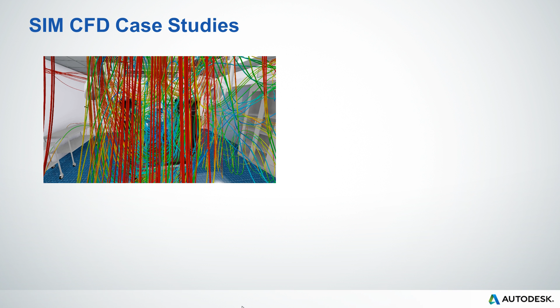The design of several configurations allows comparison of airflow patterns and provides an understanding of the sensitivity to various inputs and conditions. In this case, 8 different types of diffusers and supply velocities were explored, helping to identify the impact of moving from the minimum standard array recommended by ASHRAE guidelines to Huntair's own high-performance Clean Suite array.